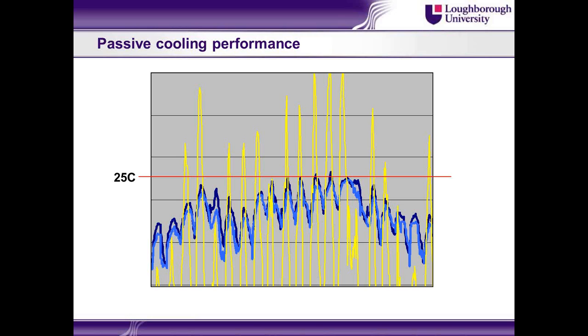But the other thing that's happened, which is harder to see, is there's a slight time lag in that peak. So although the peak temperature outside might occur at about 2 p.m. in the afternoon, the peak temperature inside may be delayed by, say, 2 hours, 3 hours. So the peak temperature inside occurs maybe 4 or 5 o'clock. People are going home. So that's a helpful phenomenon that's going on there.